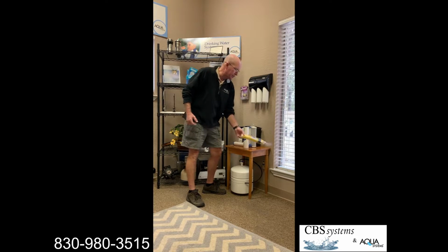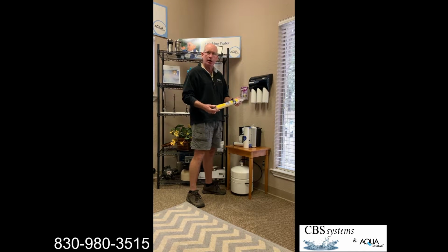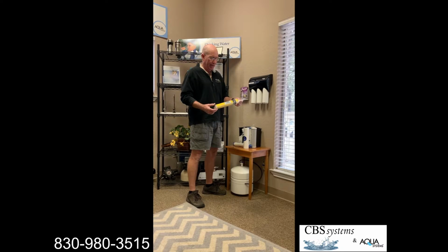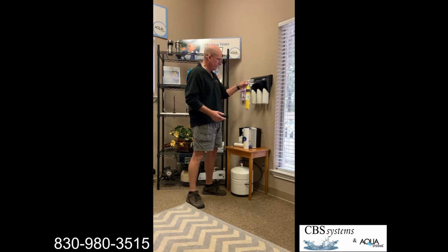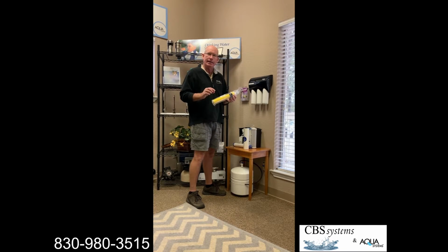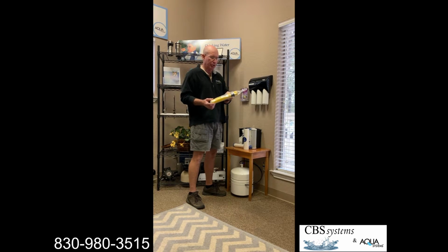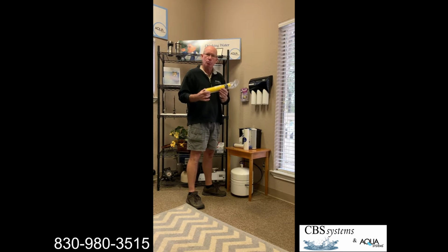The other important thing is membranes. This is what does the ultra purification, if you will. And this is usually the third stage of an RO system, whether it's 4 stages or 3 stages. Membranes are rated in gallons per day of how much water they can produce. It's critical that you match the membrane productivity per day with the drain line flow controller for the wastewater, or reject water, going down the drain. If you put in the wrong size membrane, it'll either not last long enough or it won't perform the way that you want it to.